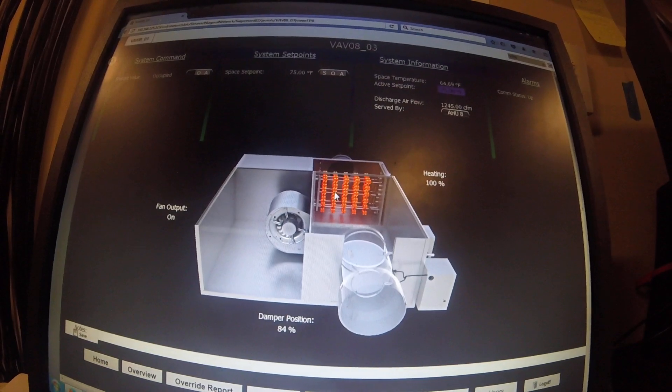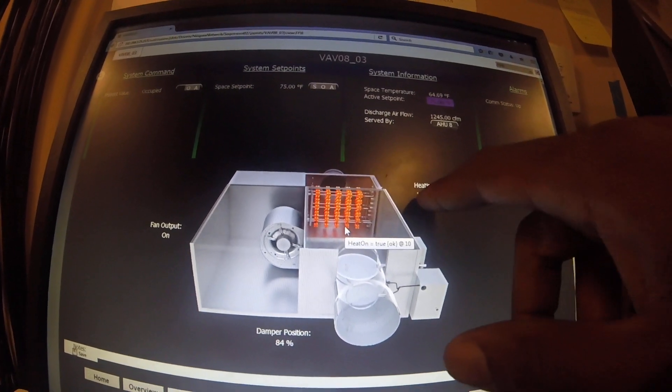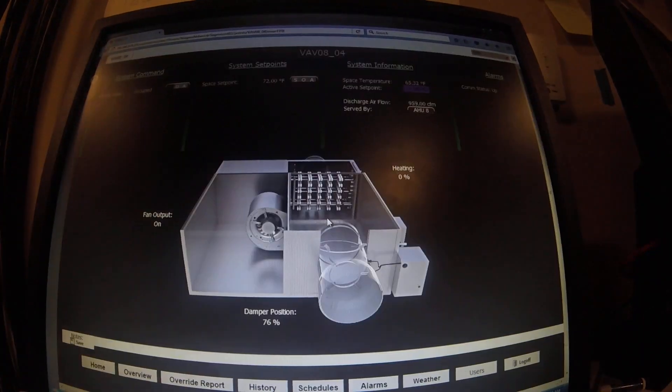Let's look at VAV 3 — same thing. See how it's lit up? Notice the difference: it's at 100%, calling for heat. Let's go back to 4 — you see that 4 is not lit up. It's not even calling for heat when it should be. I'm going to go to the VAV box to see what we've got.